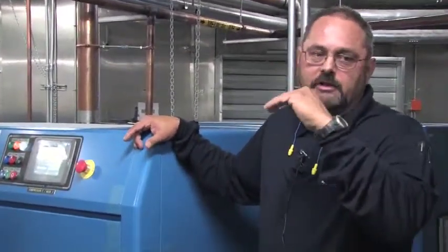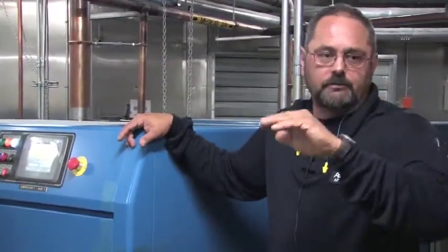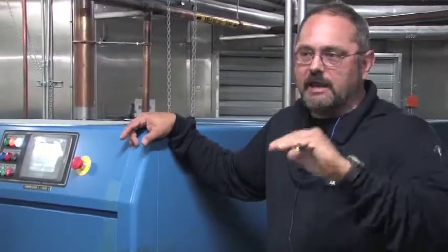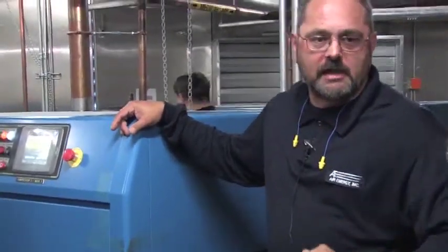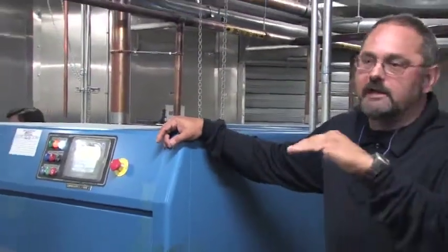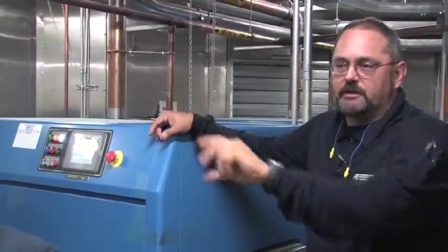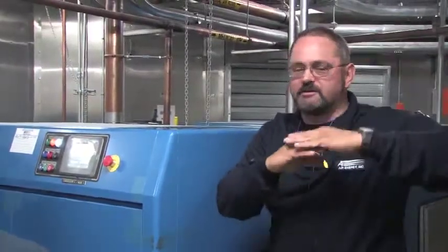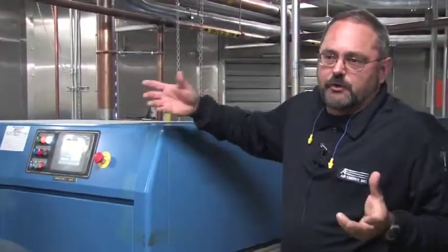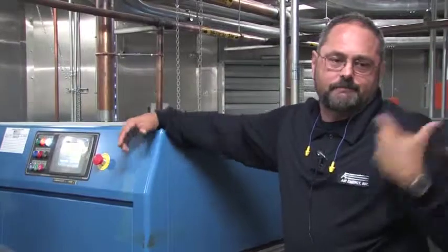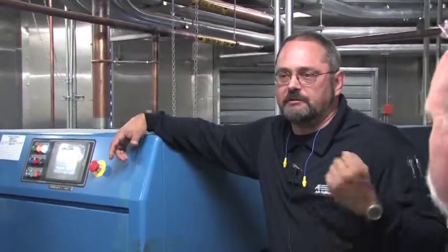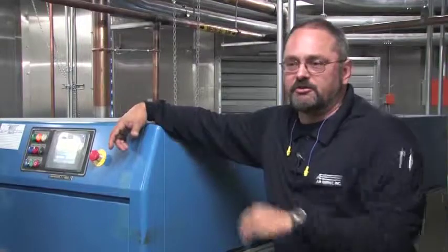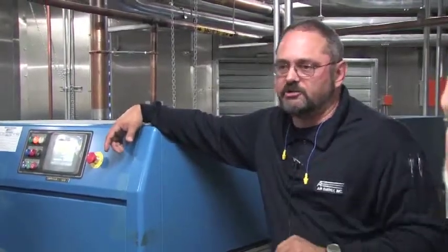The old algorithm on the other one was, on the old sequencer, you basically set, all right, our lead's gonna go 90 to 100, lag's gonna go 85 to 95, and the third one will go 80 to 90. If you look at what the bands are in there, everything's set to still go between 80, maximum drop of 80 to 100, and 110 is the fail-safe. So it's really the same thing. The difference is that since it senses rate of change and makes decisions on its own, some of those decision-making parameters may need to be adjusted a bit to cushion it.